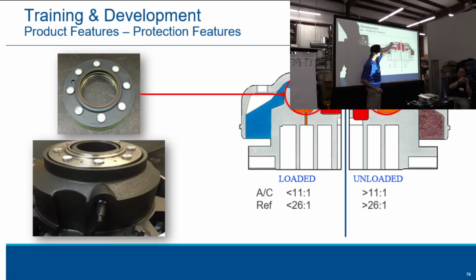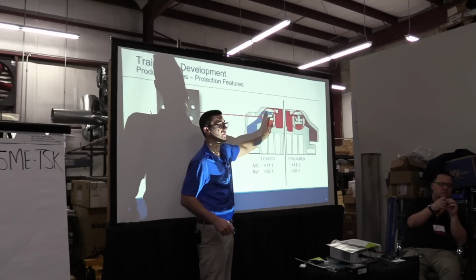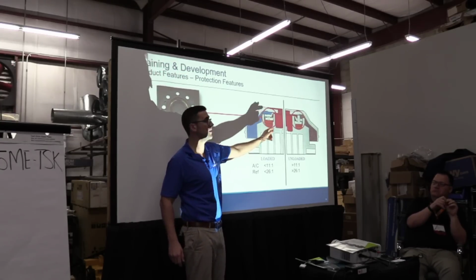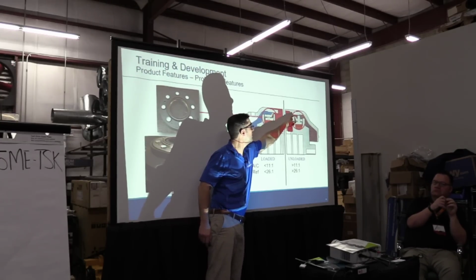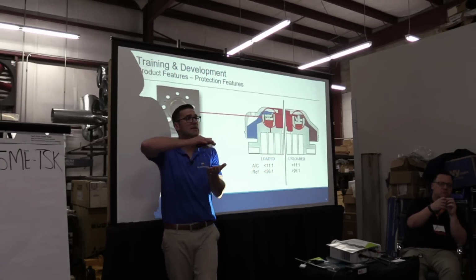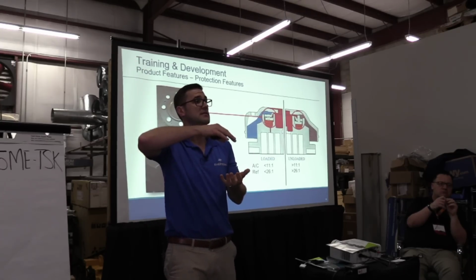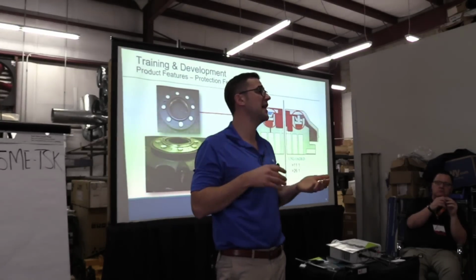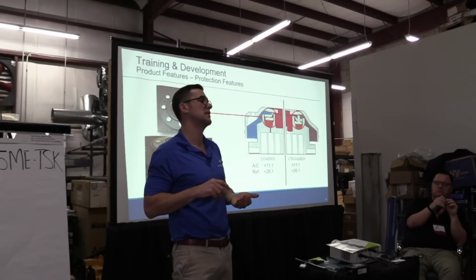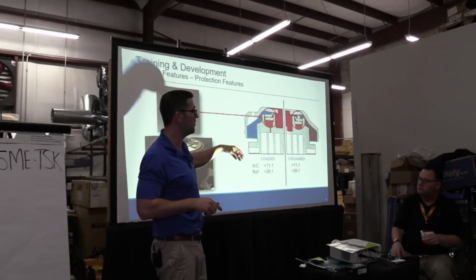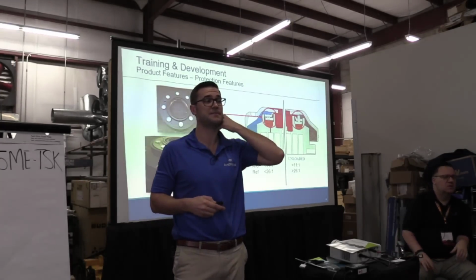See how the suction comes in up here? Here's the floating seal pushed right up against the muffler plate, and then you get discharge pressure there. That's fully pumping. But all of a sudden you'll see the floating seal not up against the plate, because it unbalances that floating seal to separate it. And we have devices sometimes to protect it. We separate them on purpose. Okay, so just remember that. Compression ratio is very important.